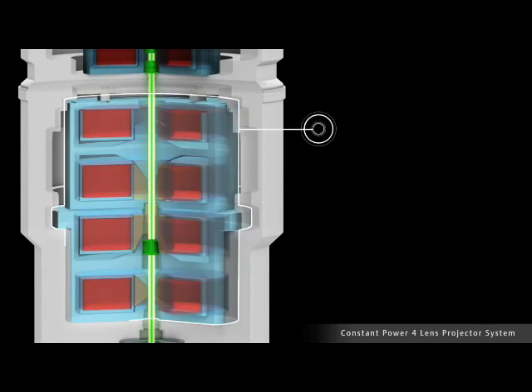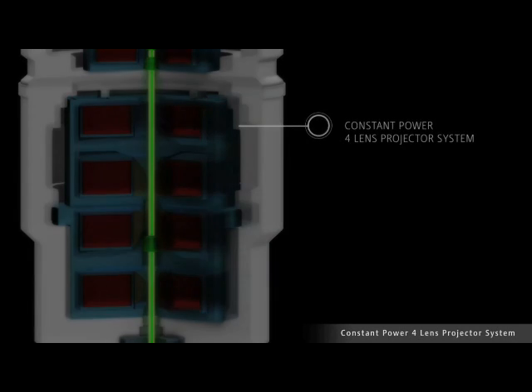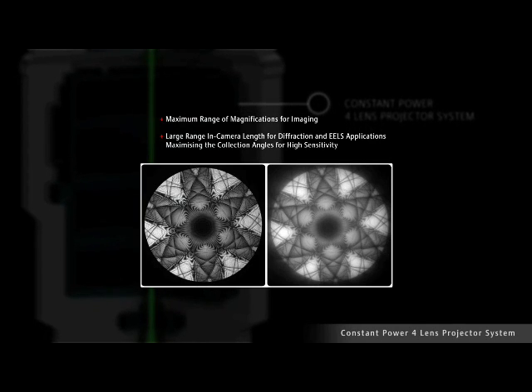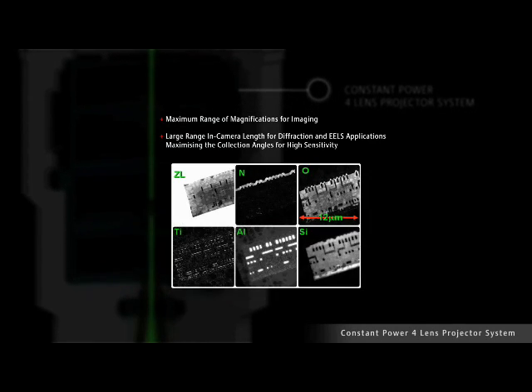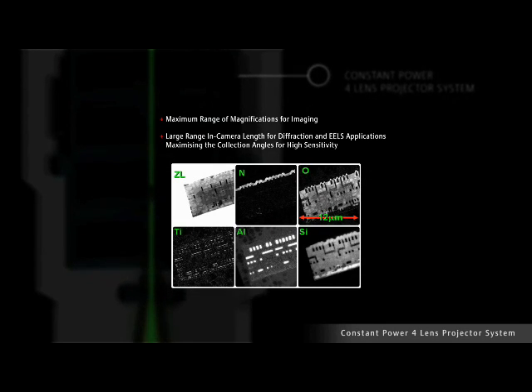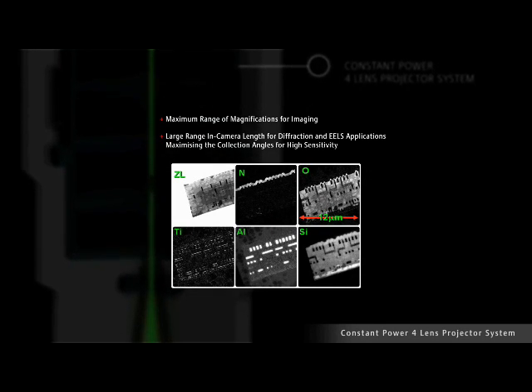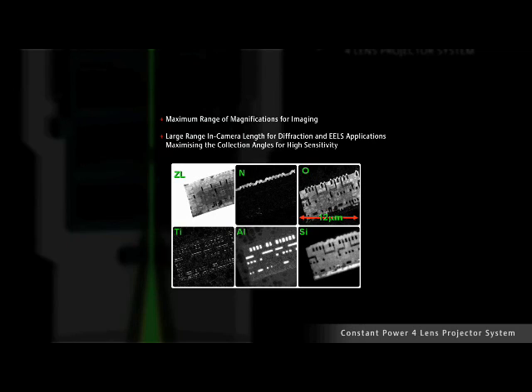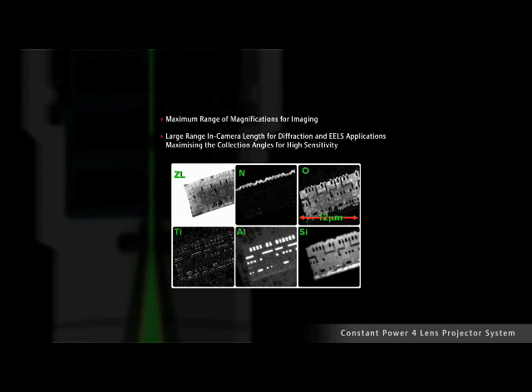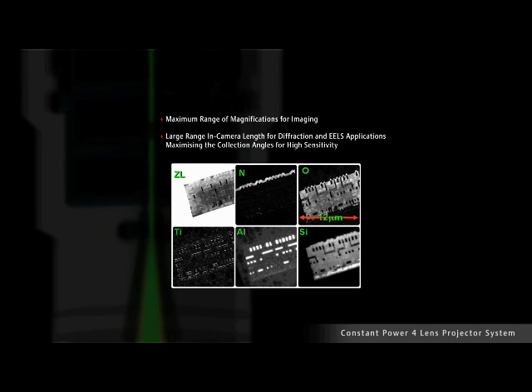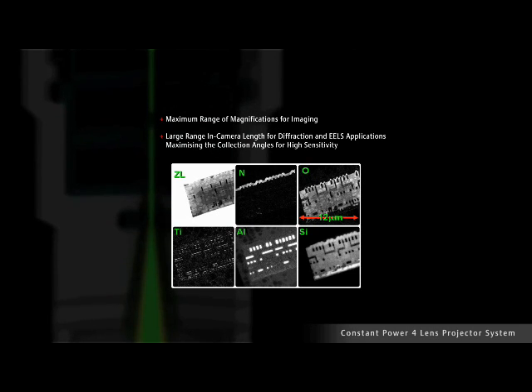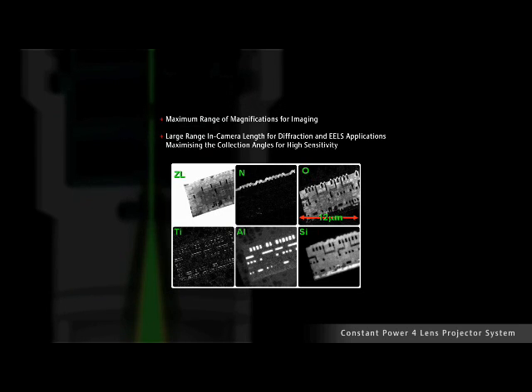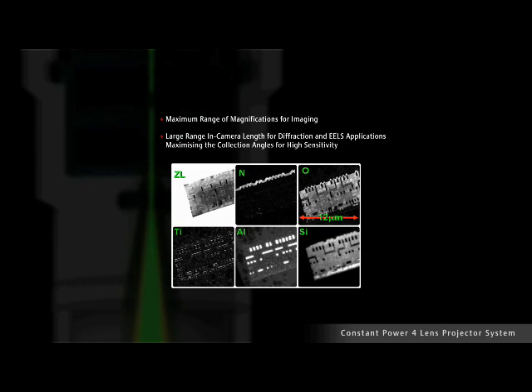The projector system is ultra-stable due to its constant power electronics and offers a maximum range of magnifications for imaging and large range in camera length for diffraction and EELS applications, maximizing the collection angles for high sensitivity. The system is not only designed to perform at extremely high magnifications for atomic imaging or spectroscopy applications as shown before, but the special post-column energy filter lens series enables one to acquire high contrast zero-loss filter diffraction patterns, large angle convergence beam electron diffraction patterns, or extremely low magnification images in chemical mapping in energy-filtered TEM of entire lamellas produced by focused ion beam sample preparation.